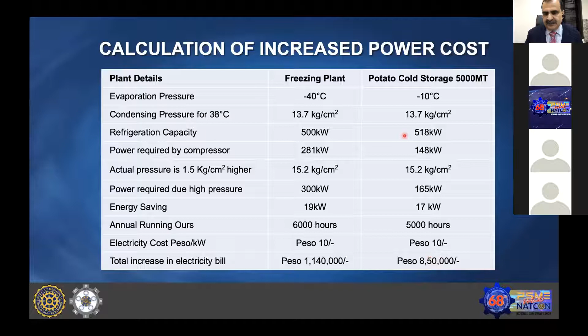In a typical potato cold storage, which is operating at minus 7 to minus 10 degree evaporating condition, for the same condensing temperature, a 5,000 metric ton potato cold storage is typically made with 520 kilowatt refrigeration capacity. The power calculation due to increase in the discharge pressure is around 165 kilowatts, and that resulted in 17 kilowatts per hour saving. And potato storage in India normally runs only around 8 to 10 months. So with 5,000 hours of operation, it saved 850,000 peso in a year.